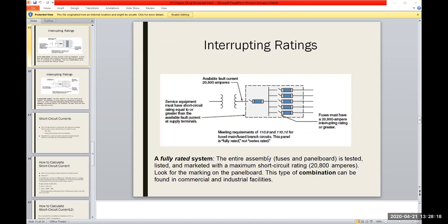So if we look at this, and this is a typical example, right? If we look at the first one, the double coils, that's basically your transformer on the line. And then coming in at the first fuse marking is your service disconnect. So that would be the main breaker on your panel.